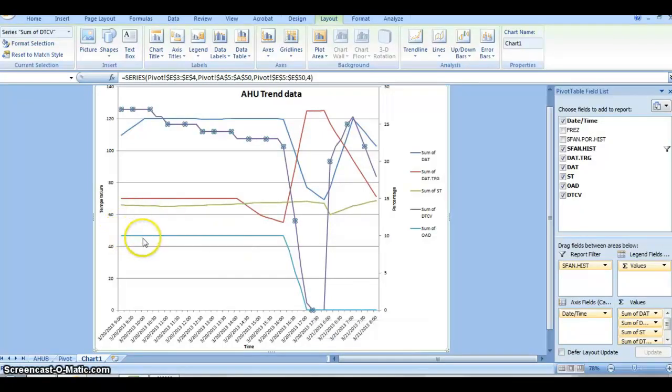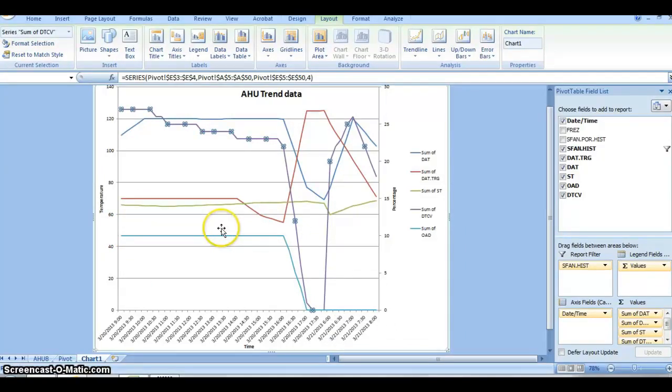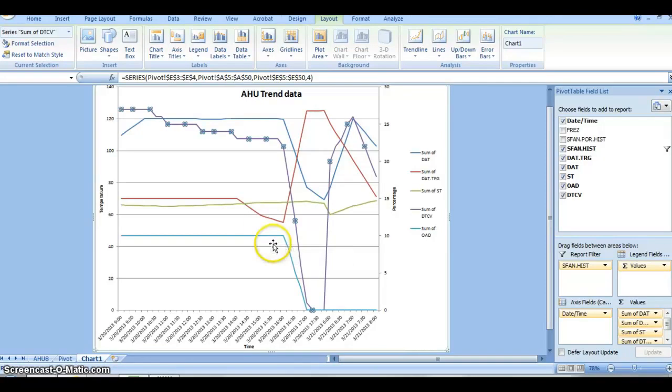This blue line here, we know that the system is ventilating when it should be, so that's 12% open, which is minimum standards, and it kicks off as occupancy starts to decrease, which is great.